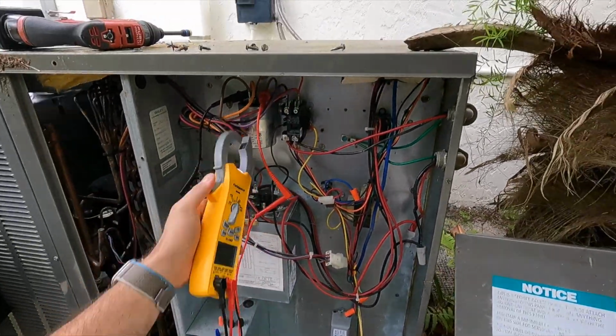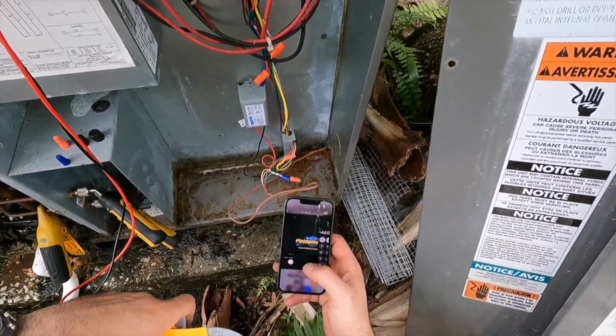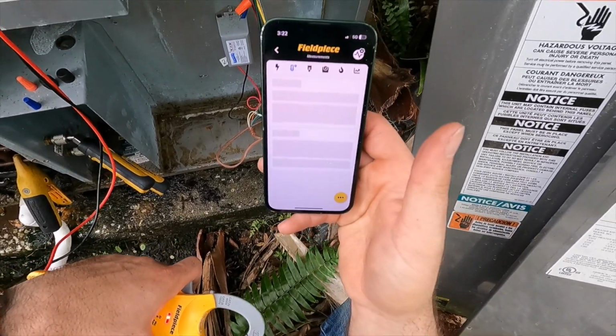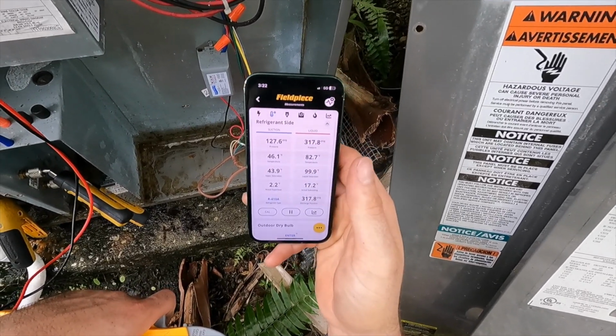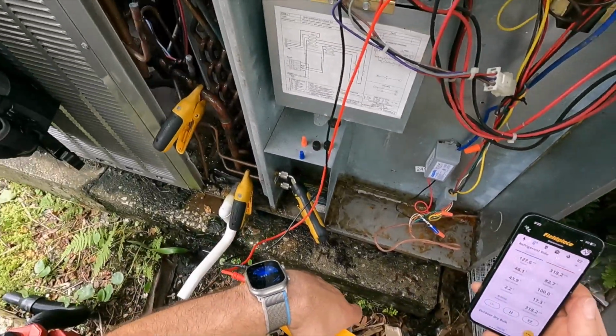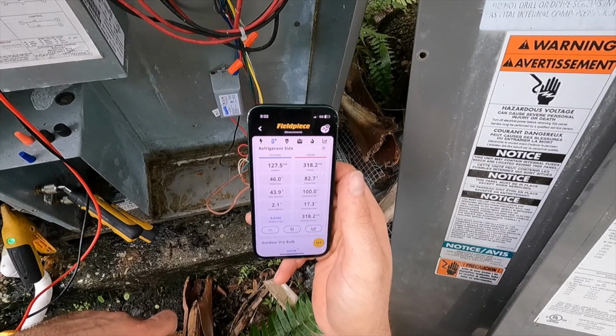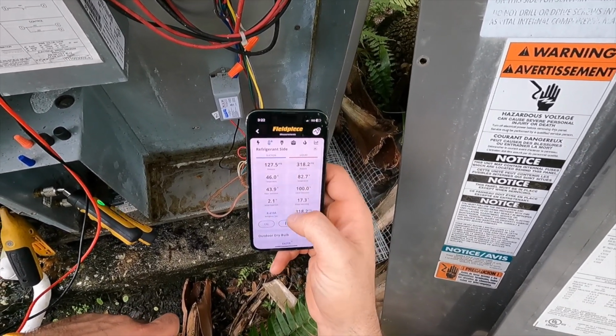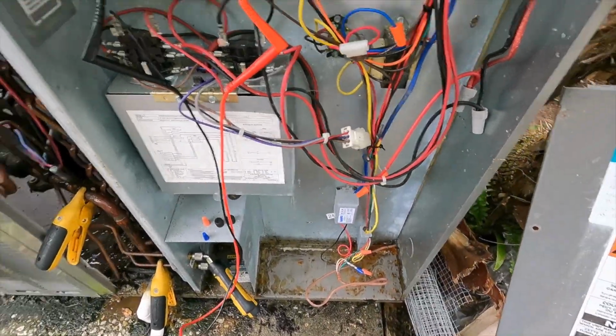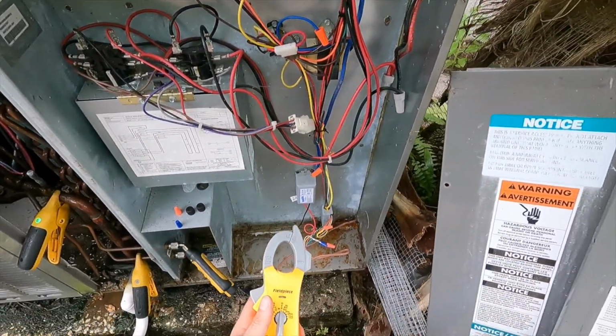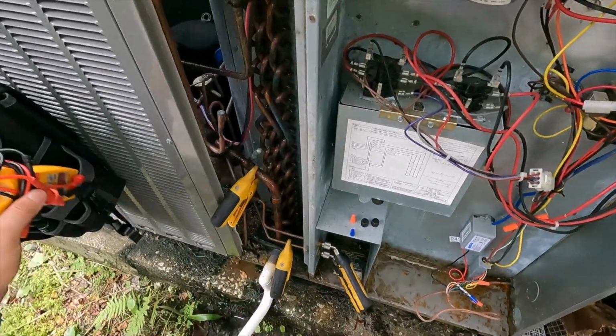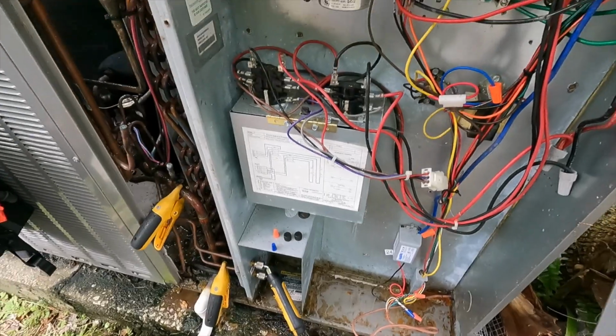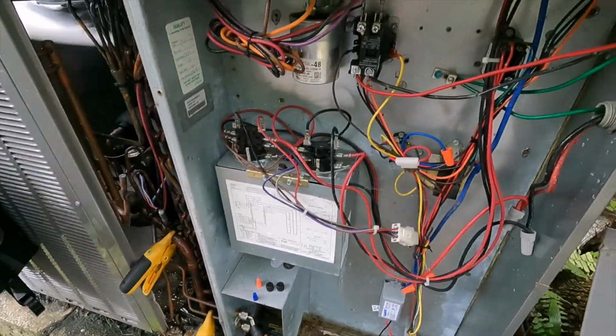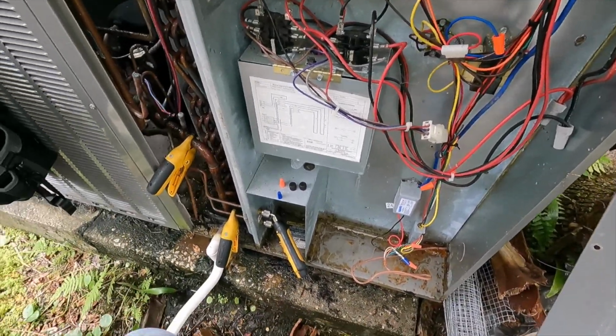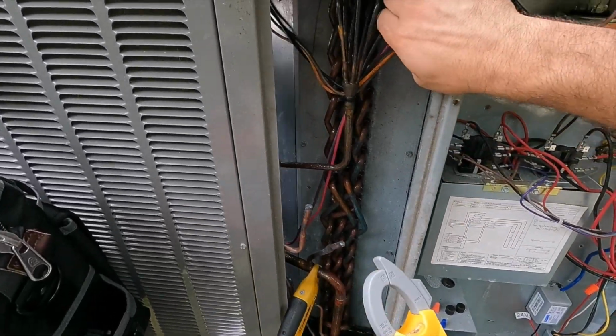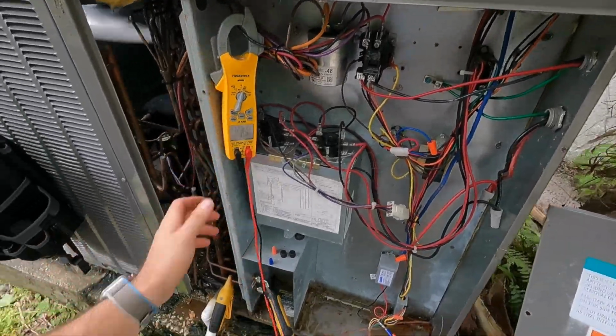We're looking good. All right, now let's go ahead and take a peek at our refrigeration cycle. 43-degree coil, 17 degrees of subcool. Superheat is low, but again, we're dealing with a package unit here. We got a head pressure of 318. So I'm gonna say check, check, check. All looks good. All right. Got that in place. All right, so I'm gonna go ahead and power this thing down so we can take a quick inrush. Oh yeah, inrush amp draw on our lock rotor. And we'll see what that looks like.